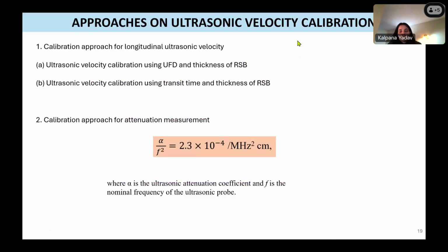There are various approaches to calibrating that device. I did a lot of testing in my PhD. If we can automate those calibration approaches, then what I did was confirm with three methods whether I get the same variation in uncertainties, and how much variation there is. The methods were ultrasonic velocity calibration using an ultrasonic flaw detector and the thickness of a reference standard block, where you can measure velocity the way I explained before in the slides, and ultrasonic velocity calibration using transit time. As we know, velocity equals distance over time. So if you measure the thickness and transit time of the sample, you can get the ultrasonic velocity. And we compare the uncertainty in the sample.